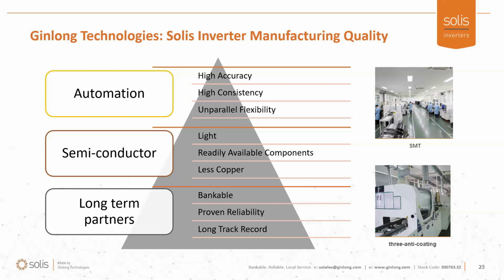Third, and more importantly, using semiconductors we use much less copper, which is getting more expensive. Semiconductors' main material is silicon, built from sand, so we're able to control our future costs much better. Copper also weighs a lot more - for example, comparing to traditional central inverters, which involve a lot of heavy metals including copper, aluminum, steel and others, they build up in weight very fast and increase the difficulty to work with. They are all hand built, manually built, and therefore a lot of failure could happen.